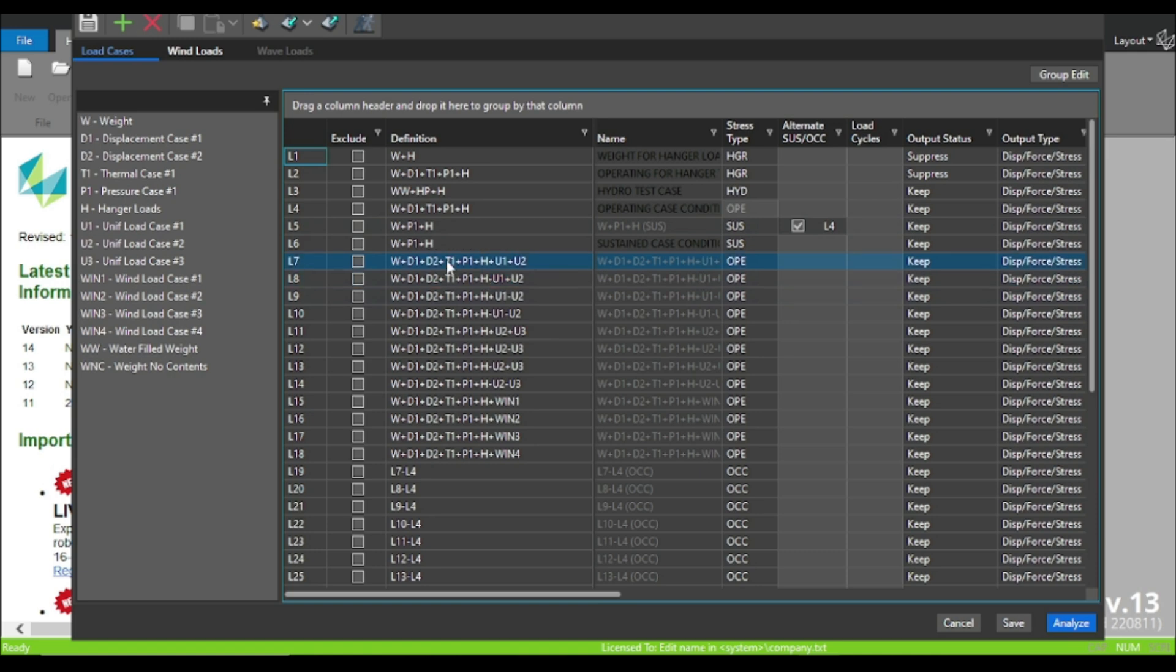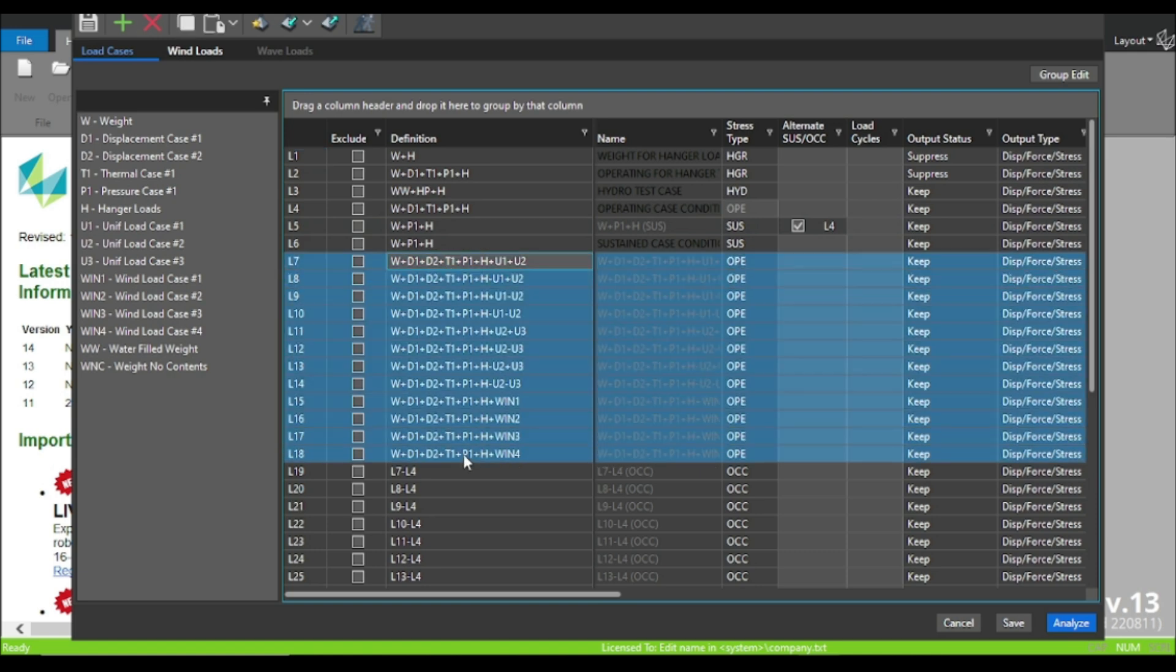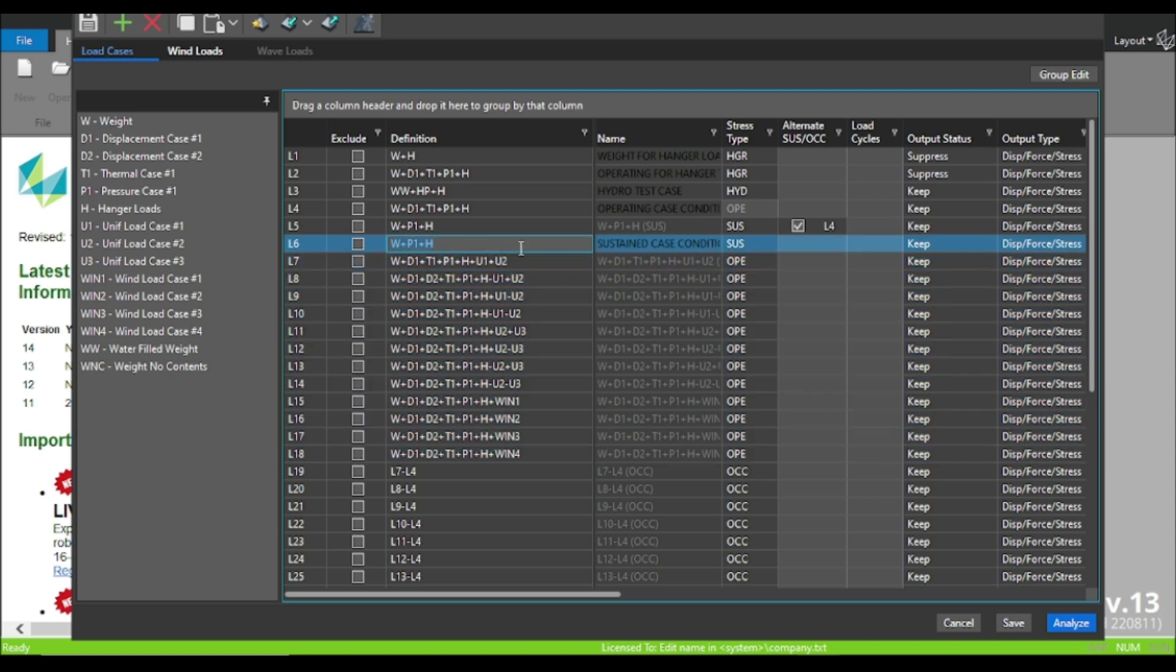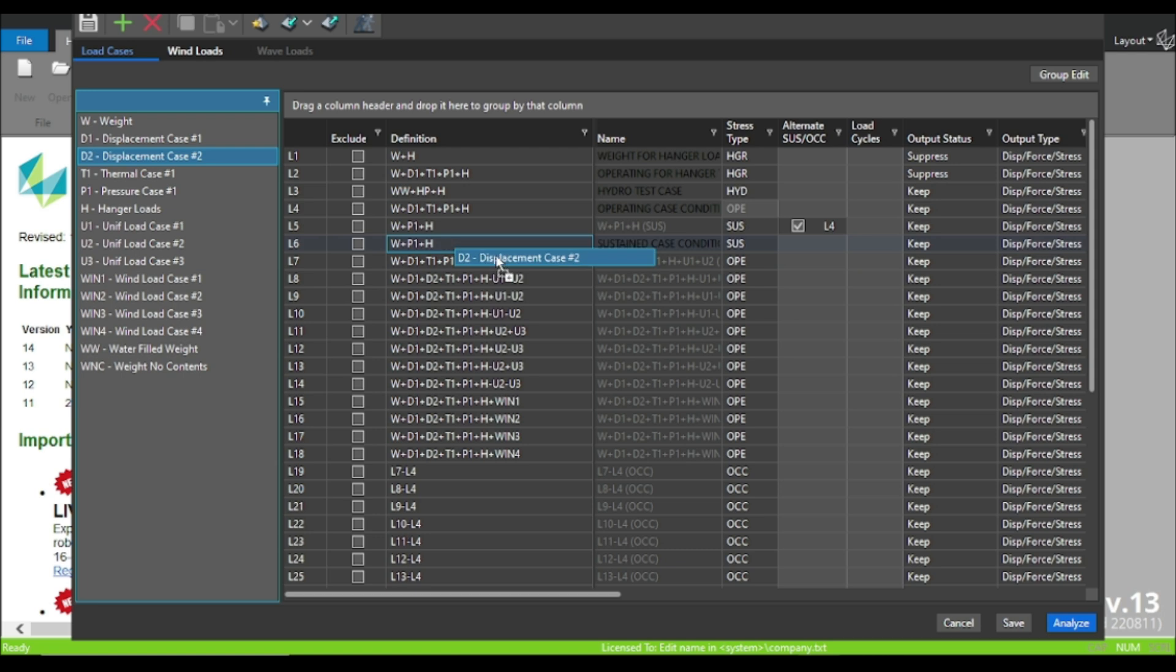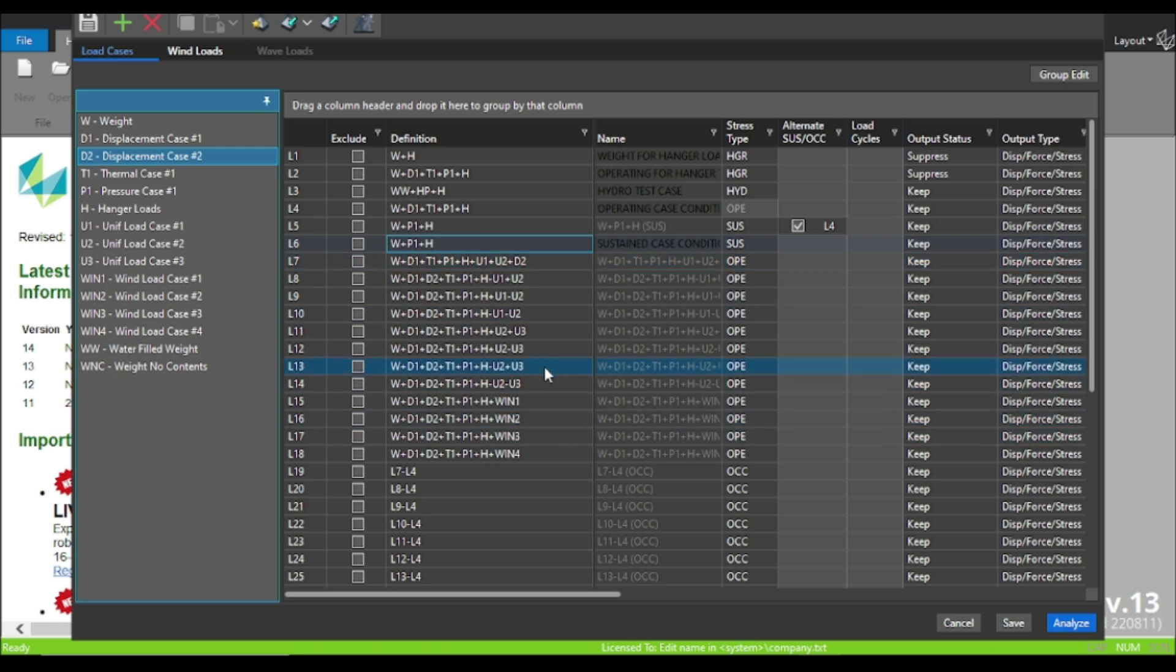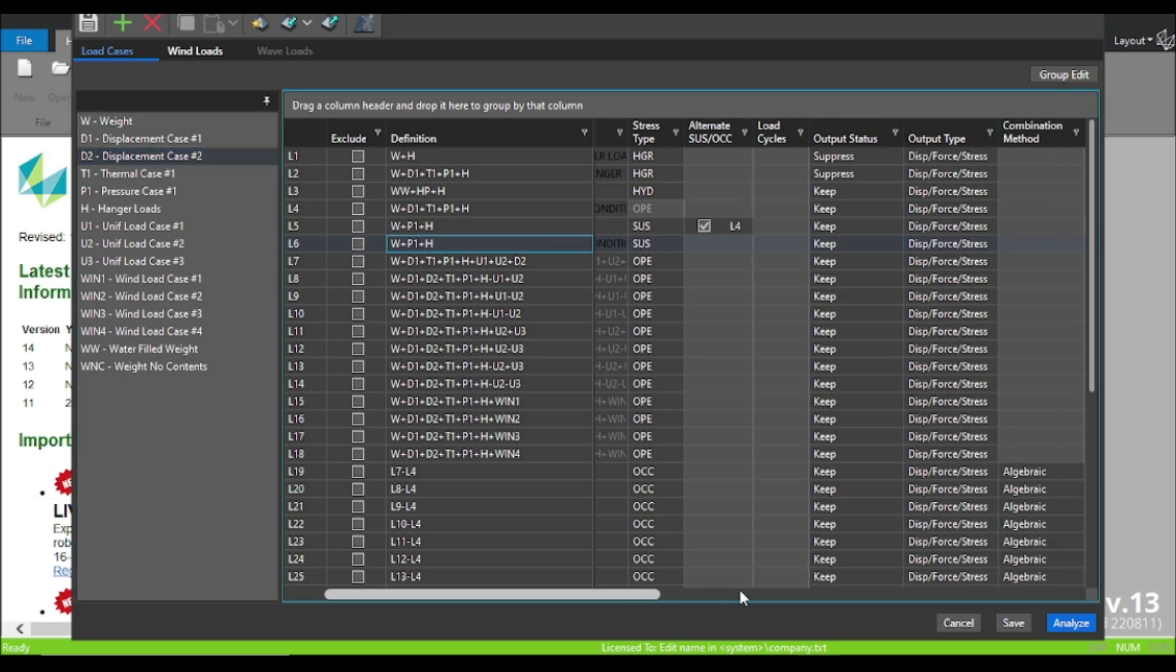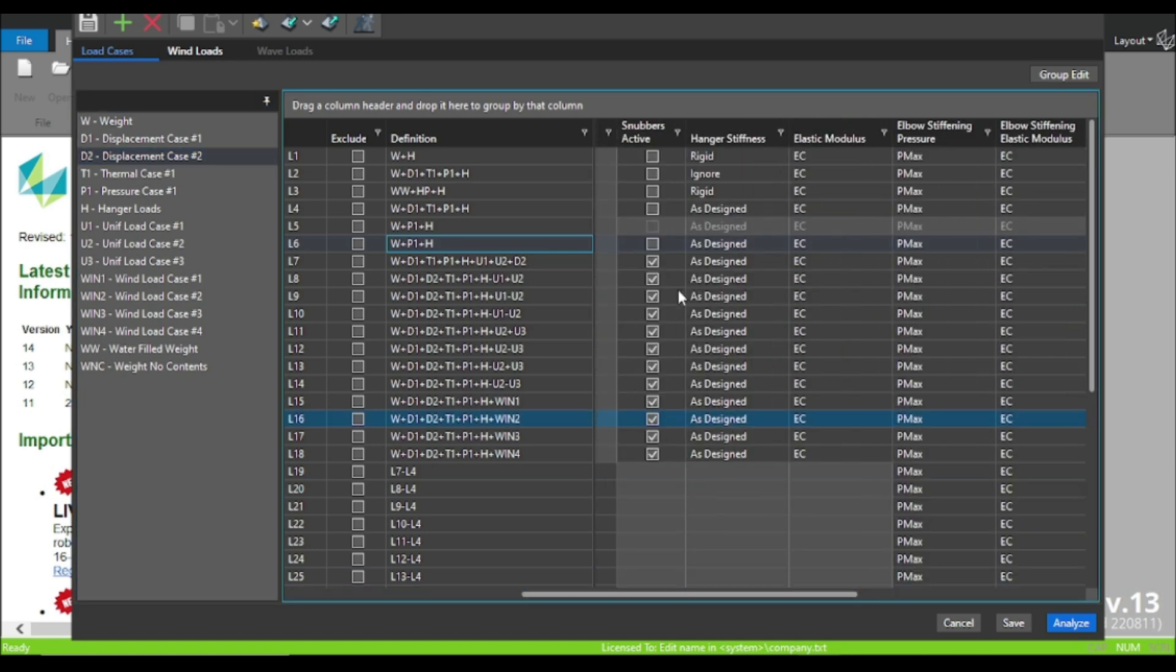Now where the occasional and operating load cases are, like operating plus seismic and operating plus wind, you have to specify the D2. I mean the snubber cases corresponding to that particular thermal case. As I am just showing one, I already done all these things. So just specify the D2. You can pause and note the load cases how I defined.